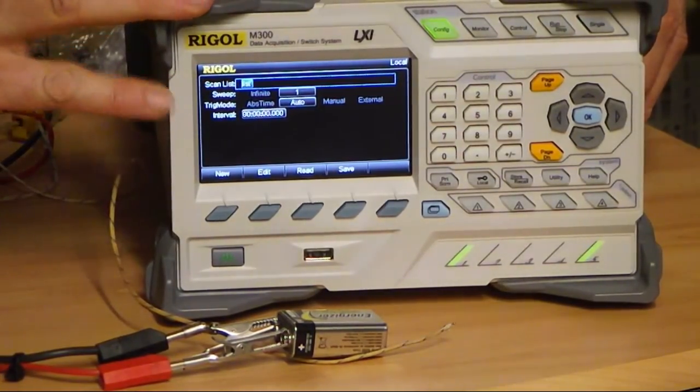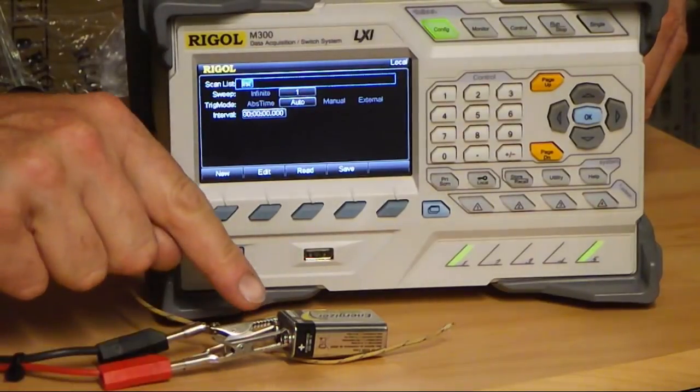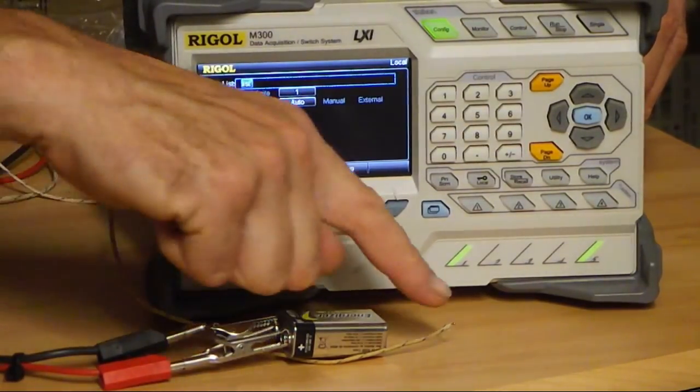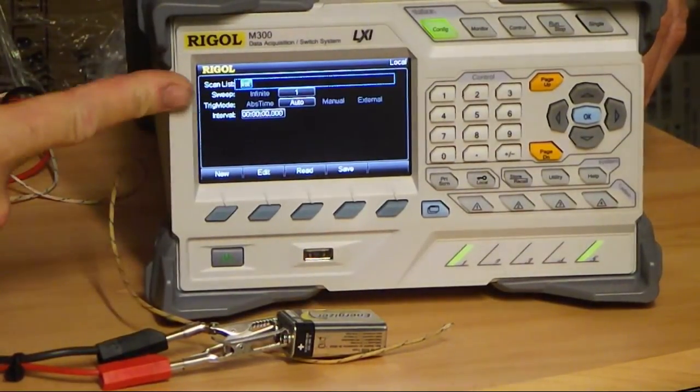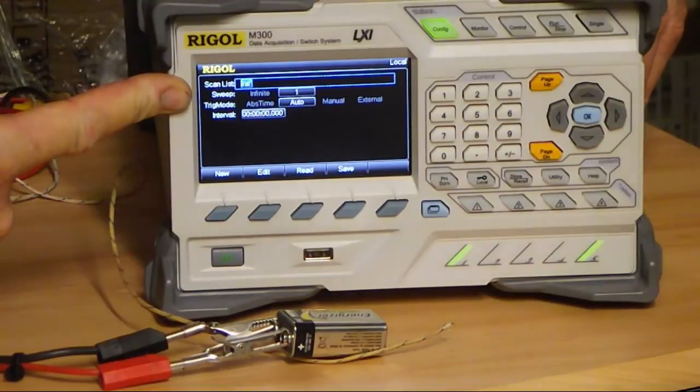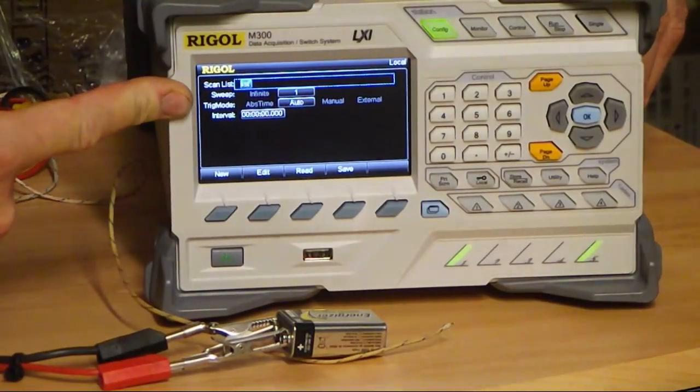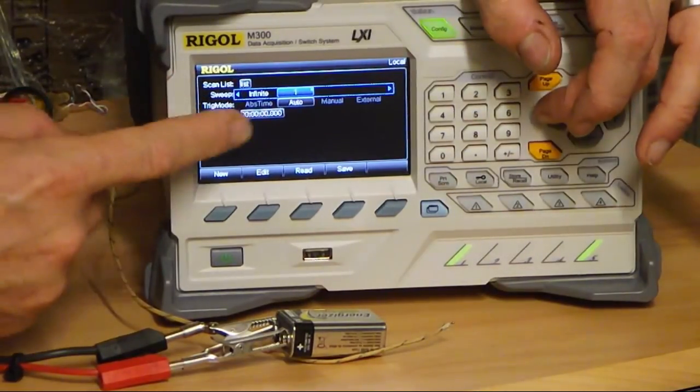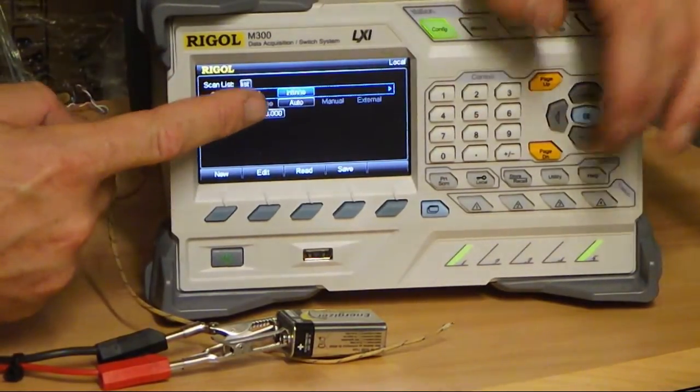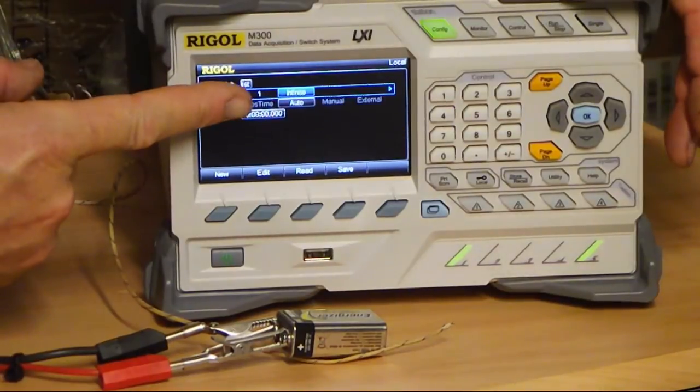And just to prove it, I've got the battery on the DC volts channel and this is the thermocouple. And what I'm going to do is to show you, this is what the scan list looks like on the front of the instrument. I'm going to set it so that there will be an infinite number of scans of those channels.